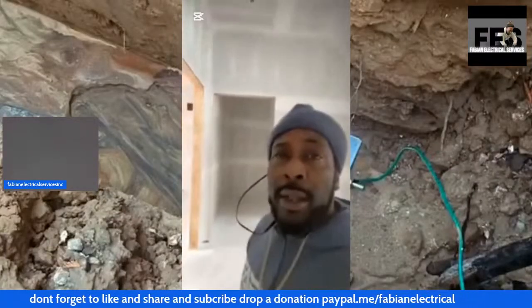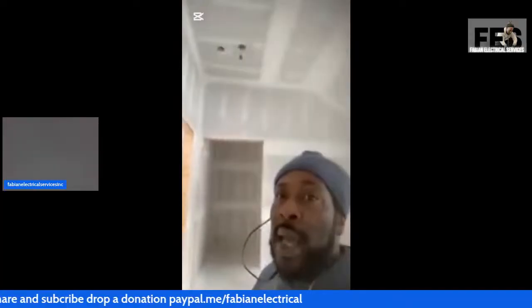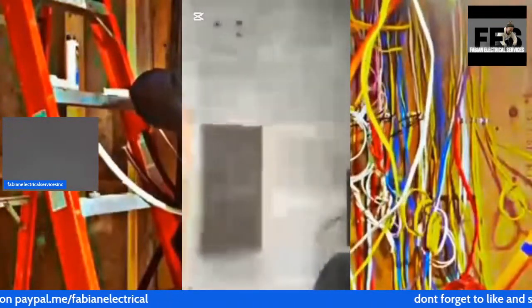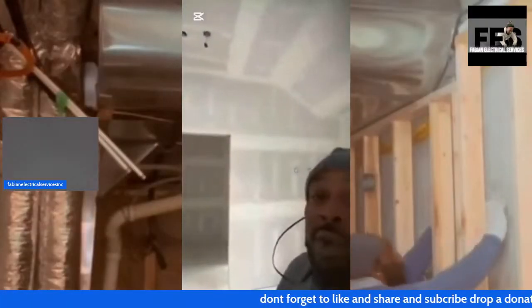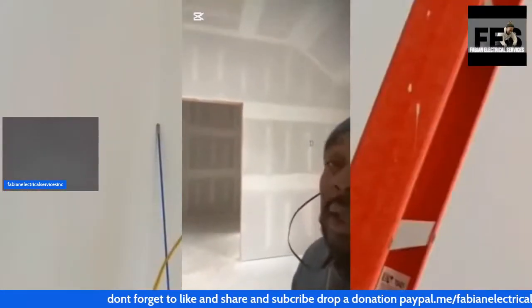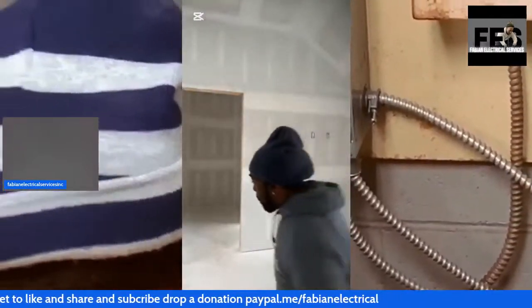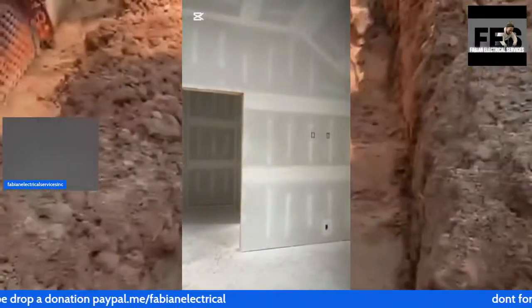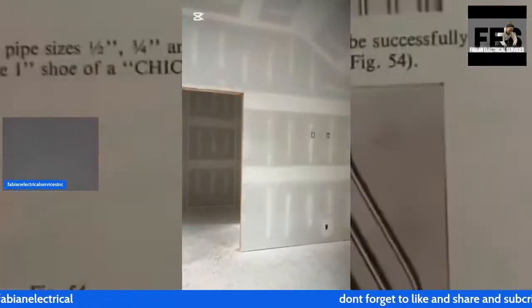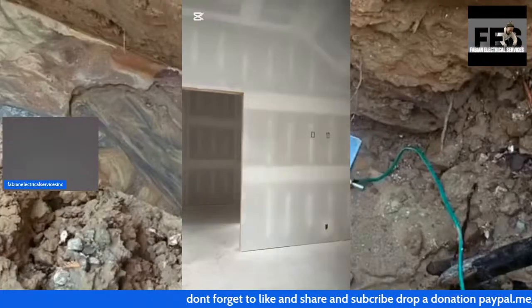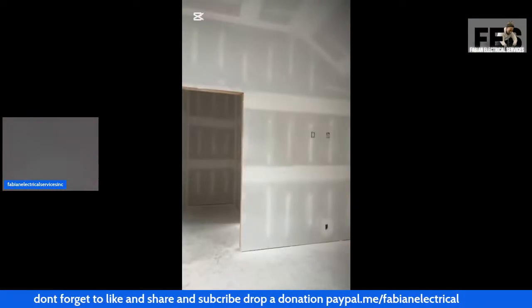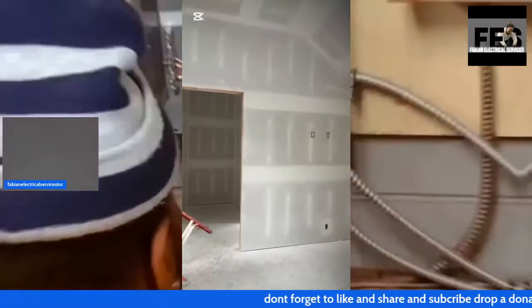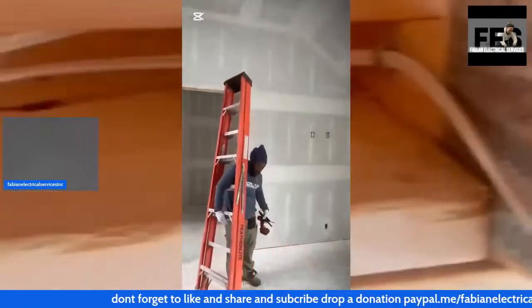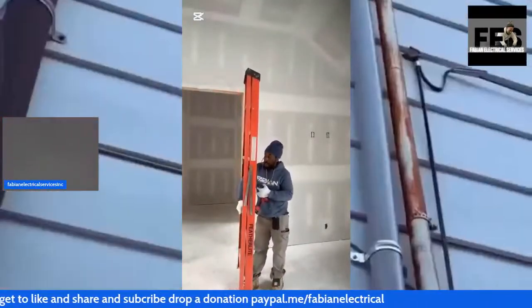So when it comes to our lighting, how I like to go about my electrical installation is to simply do a couple of lighting circuits on the floors. That way, if there happens to be a power outage, or the panel loses power on one side, at least the other lighting circuits can still be livened up and continue to work. So I always make sure I have more than one lighting circuit on the floors. This is how I like to do my installation.